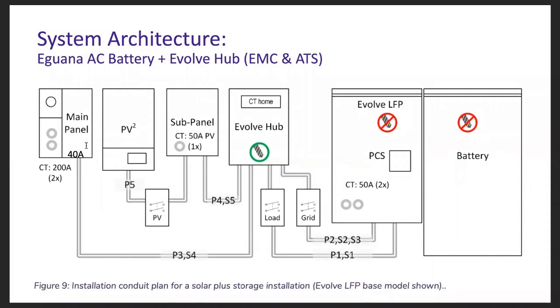In the case of our system, with the Evolve hub as a UL 1741 certified interconnection device, you can use that same 40 amp interconnection that the original PV was using and route it through the hub. Again, you would have a dedicated backup load sub panel. The PV would be landed on there, and the hub would have that 40 amp interconnection where even if the PV was off, you would still use that PV backfed interconnection. When loads were low, you backfeed into the service panel to feed other loads in the home.